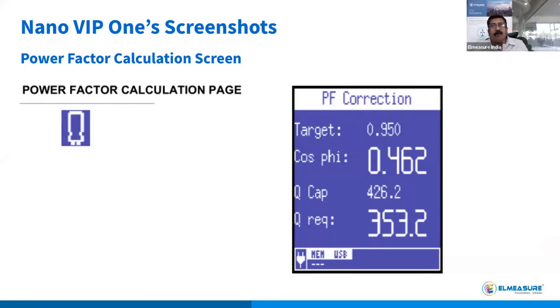Now, an important feature of this product is it handles power factor calculations. We know the norms set by the government say your power factor should be well within 0.9, between 0.9 and 1, or maybe 0.95 to 1, and you get an incentive if you maintain a power factor of 0.99.